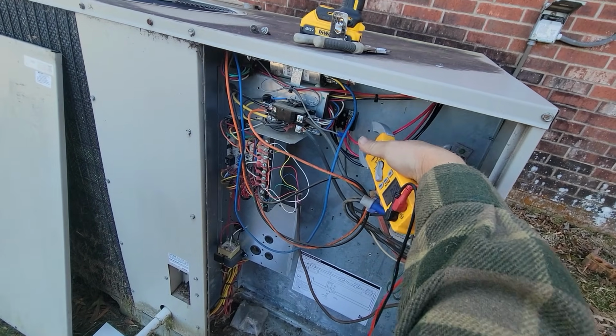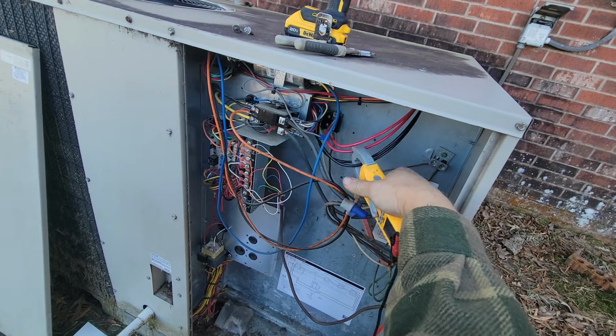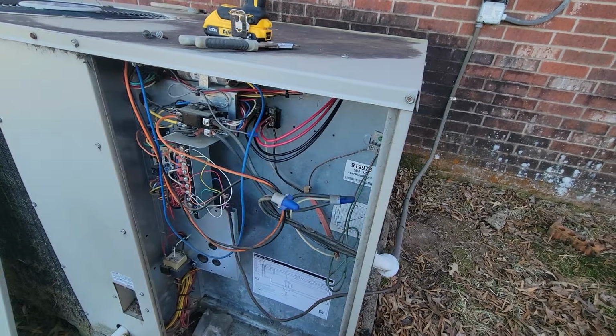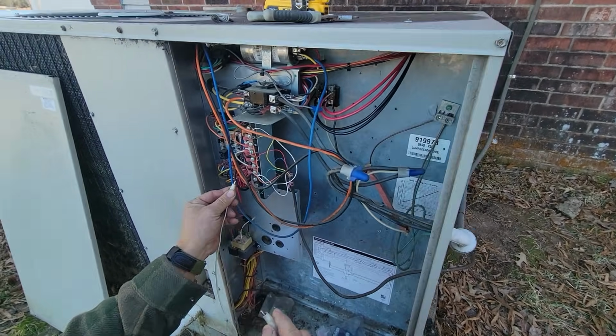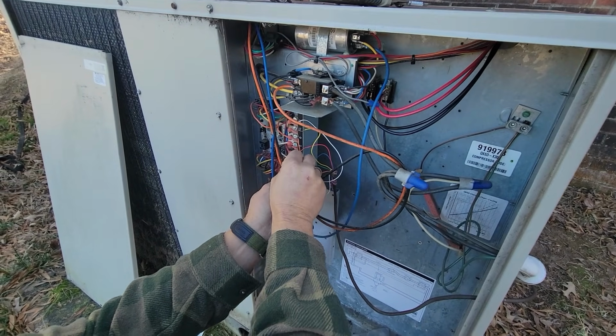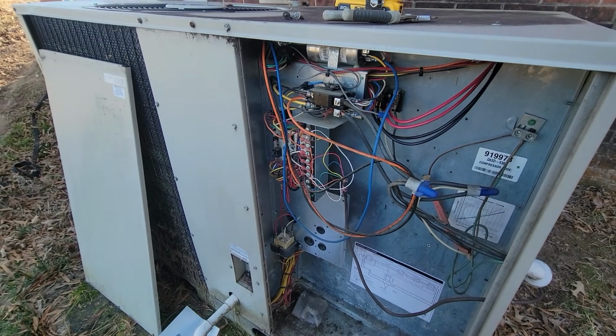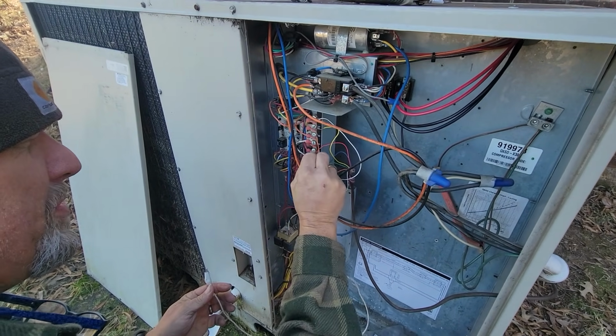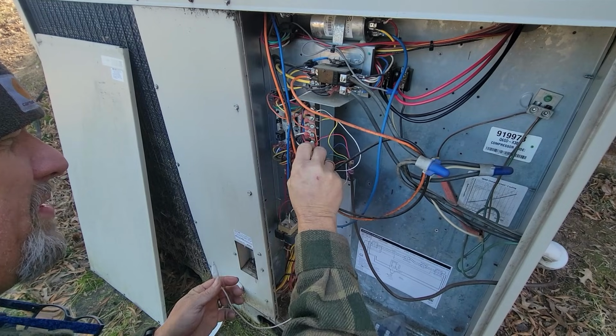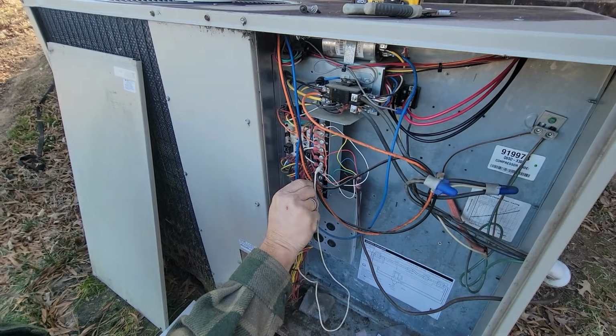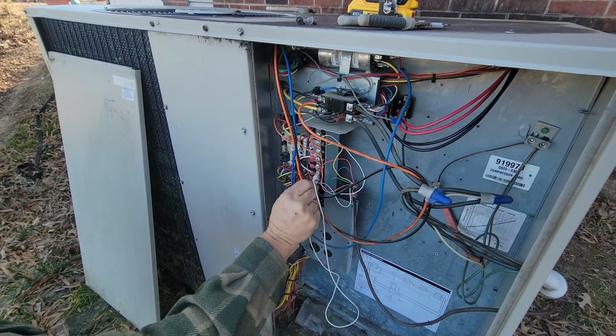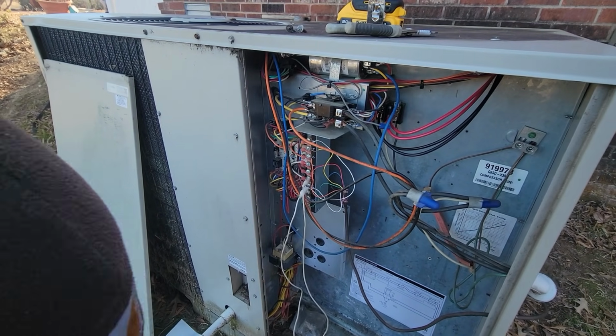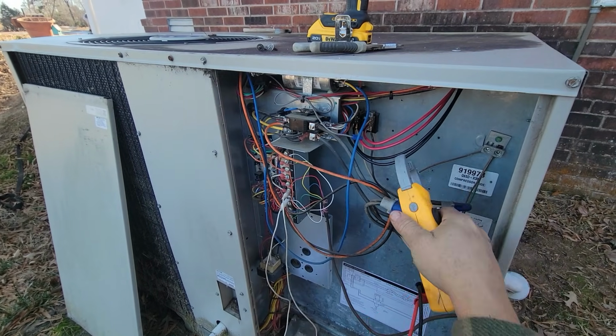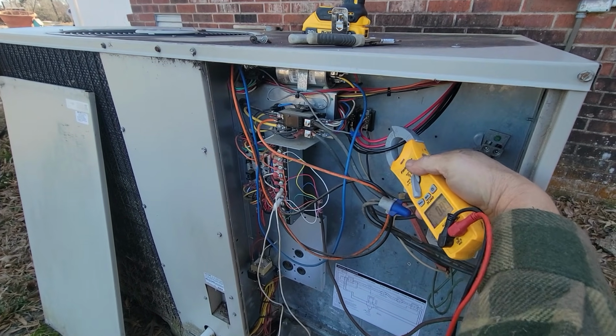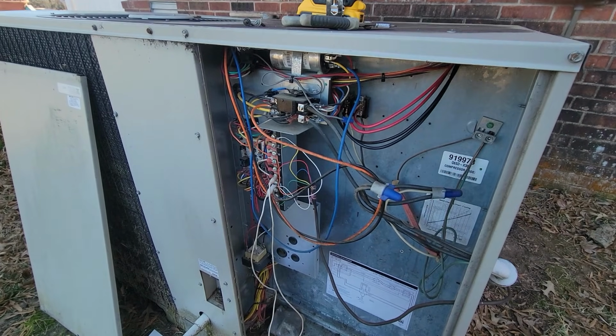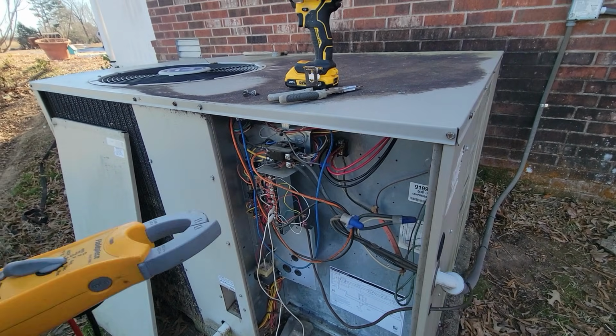No, nothing. Nothing. So let's jump again, between R, which is our 24 volts, and our W. I don't even hear the contactor click. So let's go to amp draw. Amp draw tells us if we're doing anything, and it's not. So let's take off this panel and find out why that is.